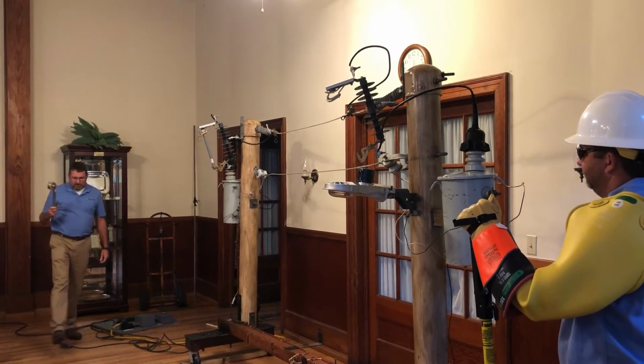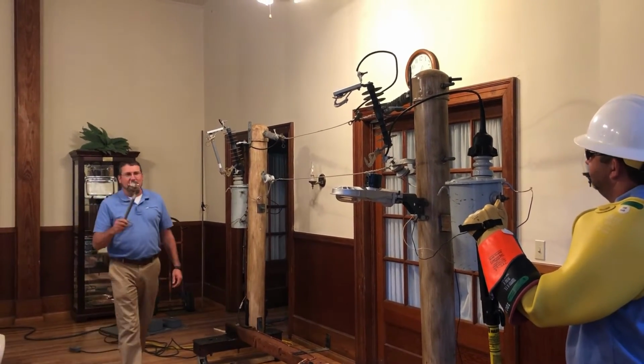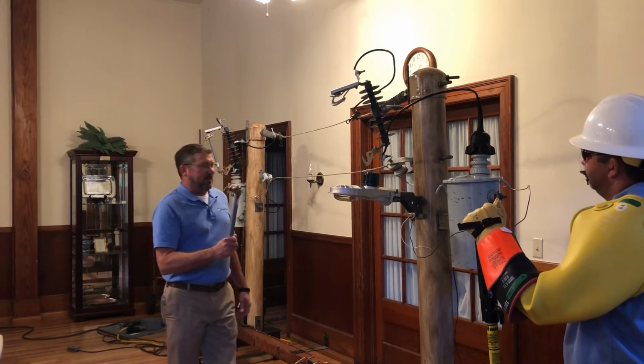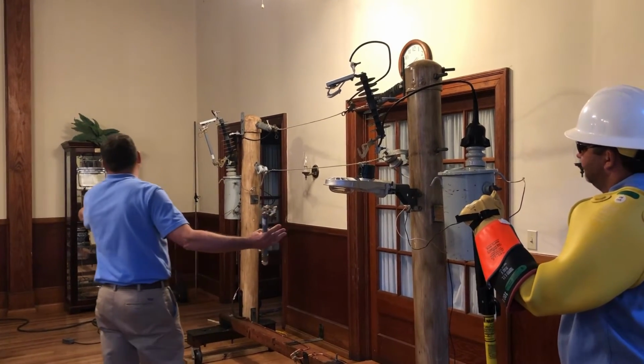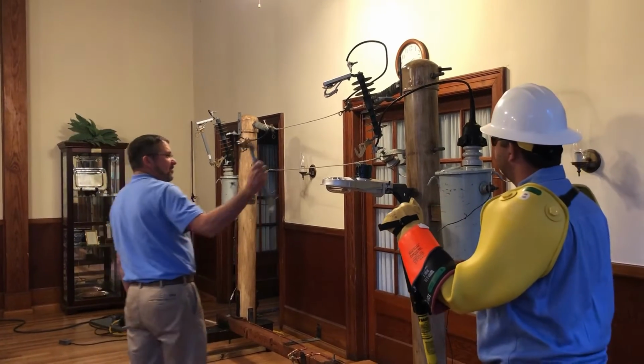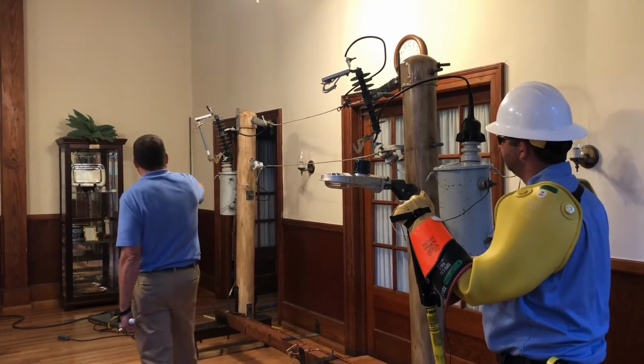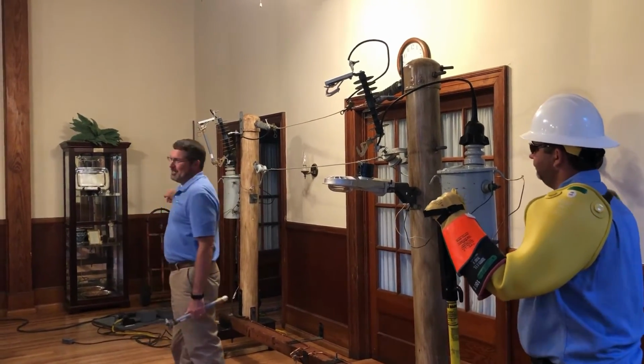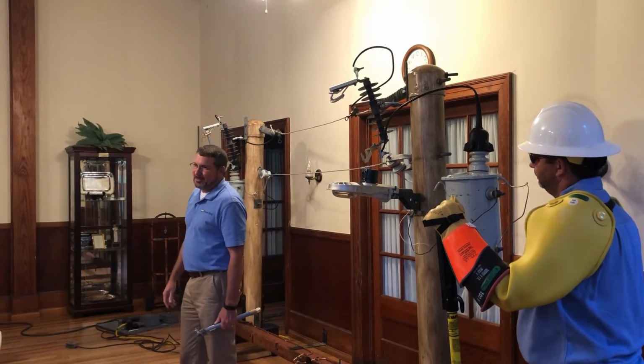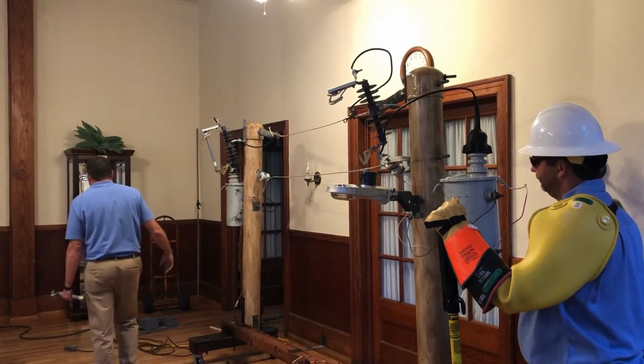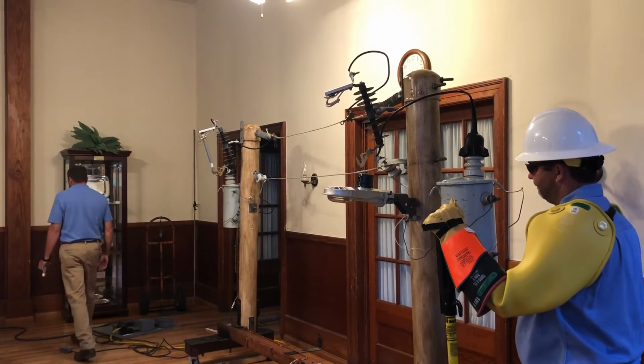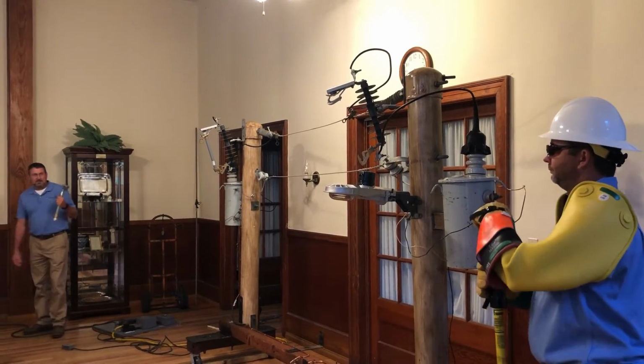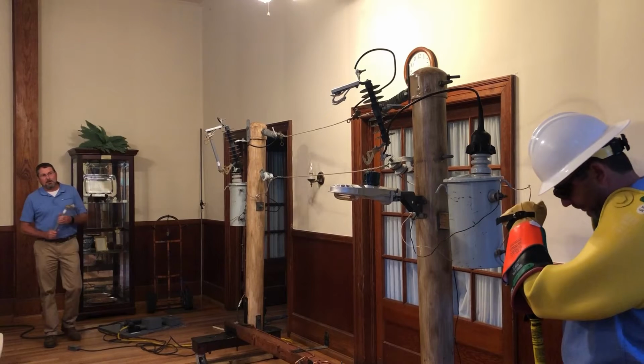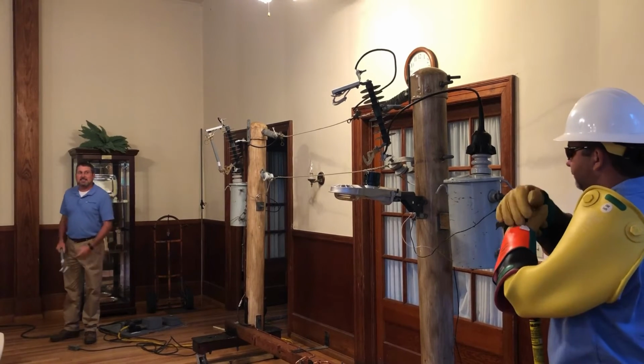Even if this fuse was out in this scenario, if these happen to be two neighbors right here, if this fuse was out, that line could still be hot because this neighbor's running his generator. So you can never take for granted that just seeing it out, or knowing you're out of power, means the line's dead.